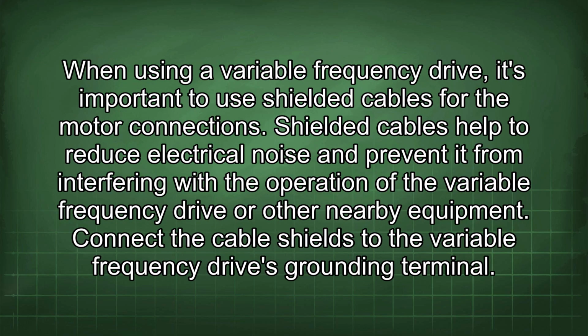When using a variable frequency drive, it's important to use shielded cables for the motor connections. Shielded cables help to reduce electrical noise and prevent it from interfering with the operation of the variable frequency drive or other nearby equipment. Connect the cable shields to the variable frequency drive's grounding terminal.